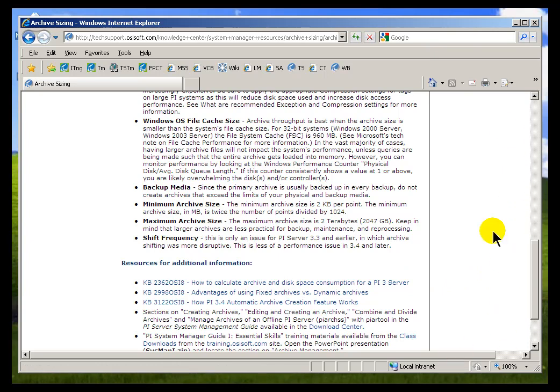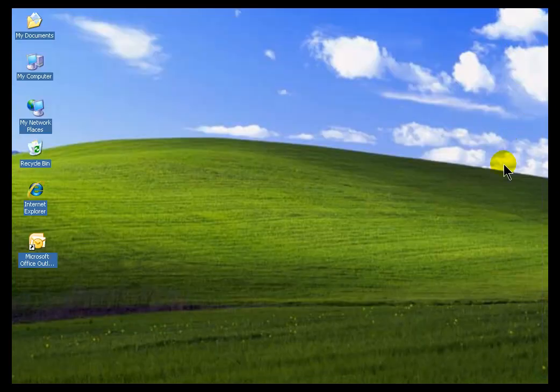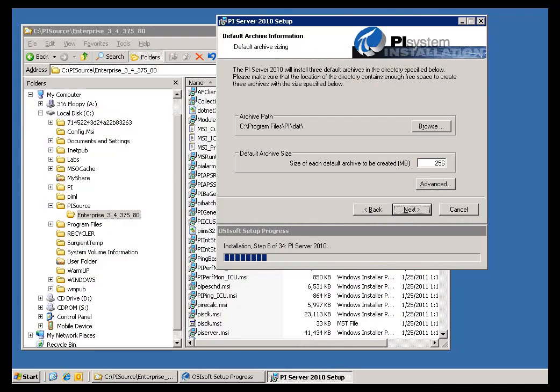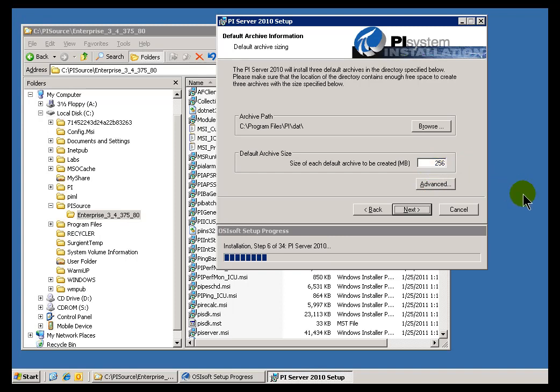What I would recommend is go ahead and do the Sizing or accept the defaults that we see right here, but then check back and take a look using the System Management tools we're going to look at later in class. Take a look at what you're storing in each individual Archives in terms of how many days worth of data. We're shooting for something like maybe five days to two weeks worth of data per Archive, something that's going to be manageable so that you're not backing it up too much, and something where you're not putting all your eggs in one basket. You don't want an Archive size so large that you're storing three, four weeks of data, maybe a couple of months of data in one Archive. There are people who accidentally delete their Archives, and it's human error that can crop up.